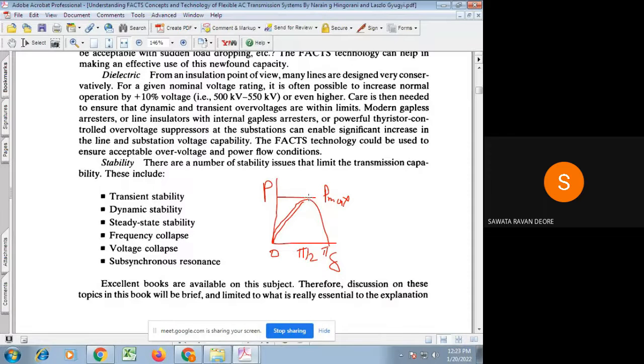That is why the system is operated at a load angle delta such that if any changes in the load happen, it will be able to regulate by maintaining synchronism. So this is the loading condition, the electrical output delivered by the machine at a load angle delta. Under these circumstances, if any variation in the load happens, delta will increase and accordingly the P delivered by the machine will increase. If the load is decreased, the electrical output of the machine will be decreased by reducing delta. So that is possible. That's why, in view of keeping steady state operation in mind, the operating angle delta can be less than 90 degrees.